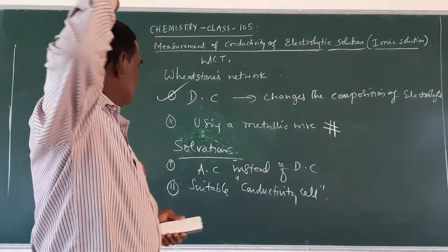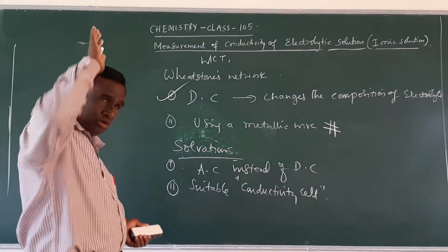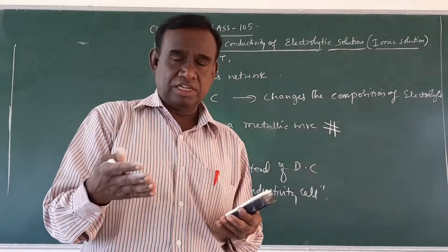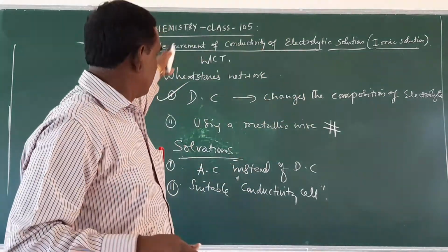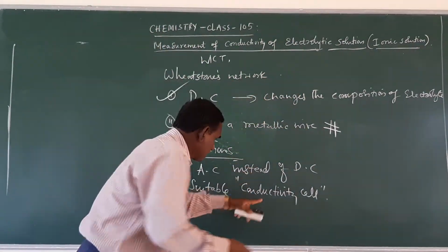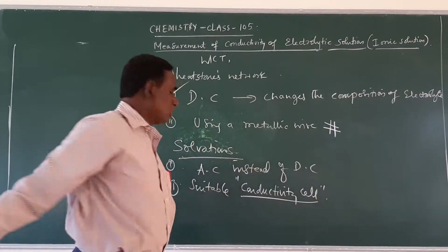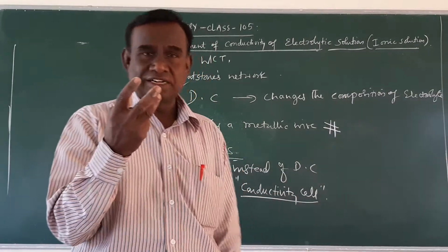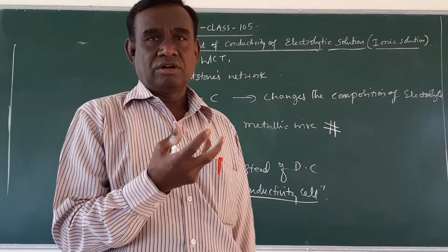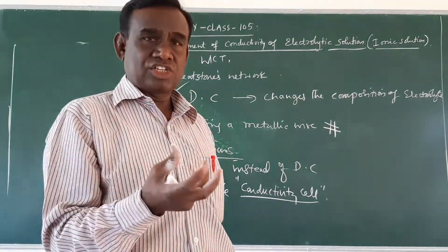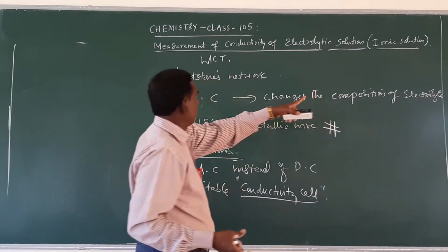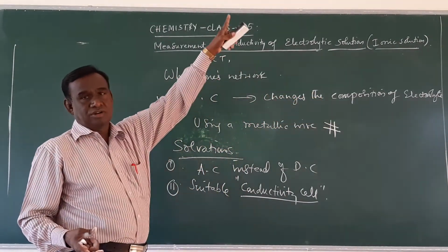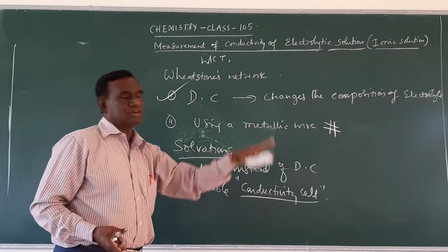That means the electrolytic solution can be connected to Wheatstone's network through this conductivity cell. It is a specially designed instrument or cell which is used to connect the electrolyte solution with the Wheatstone's network through this conductivity cell.